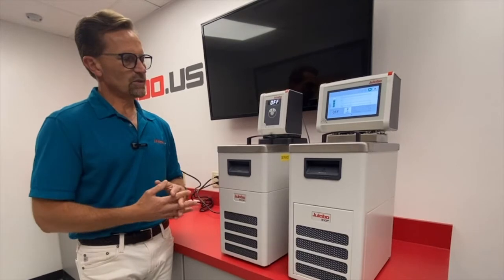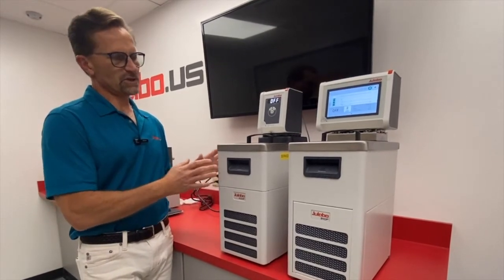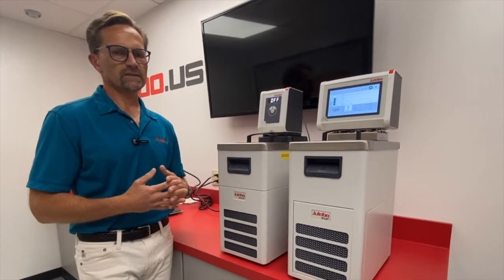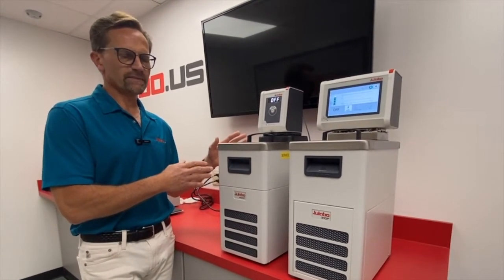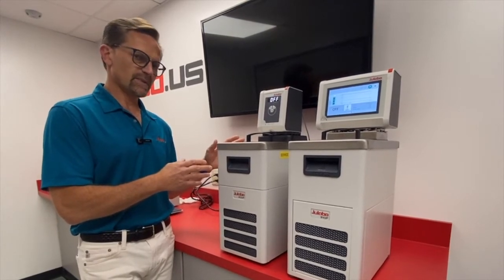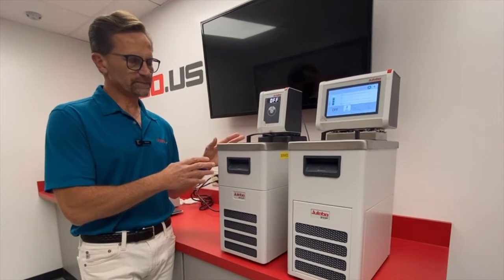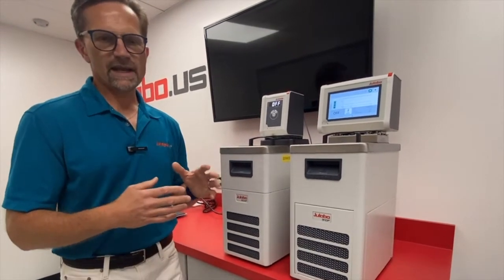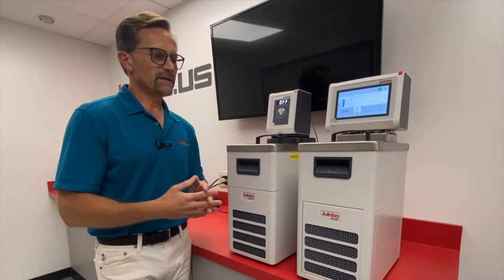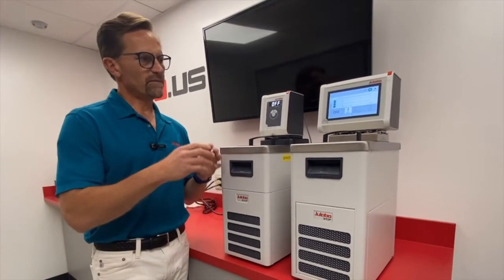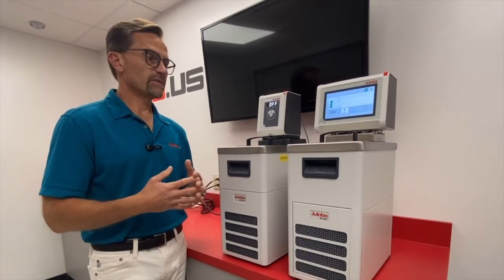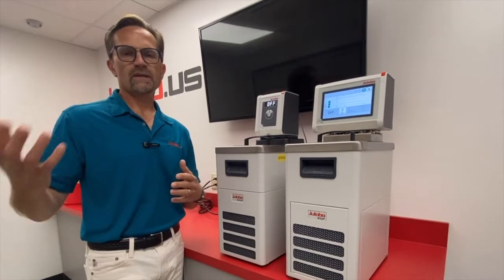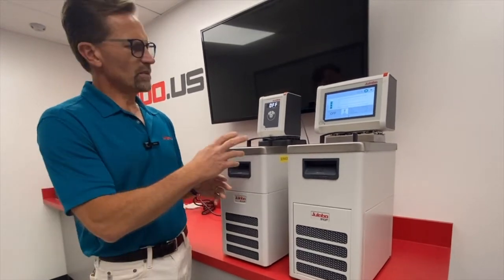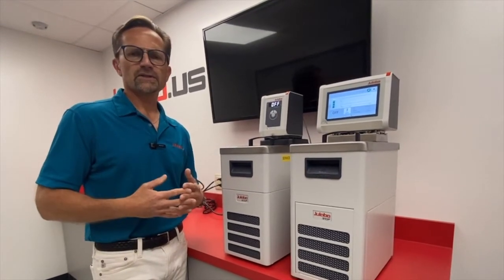So when would you decide to choose one or the other? If you have basic temperature control applications that you don't need a lot of bells and whistles, the CORIO CD is a good choice for that. It has plus or minus 0.03 degrees C stability with only 1 point calibration. If you need a lot of input-output data capture integration to other devices, the MAGIO model is the way to go, because you have programmability. You could have multi-users. For example, if someone is running a process and you only want them to have the capability to turn the unit on and off, you can set permissions for them to do that. MAGIO has all these I/O options, enabling integration into a variety of PLCs and operating systems.